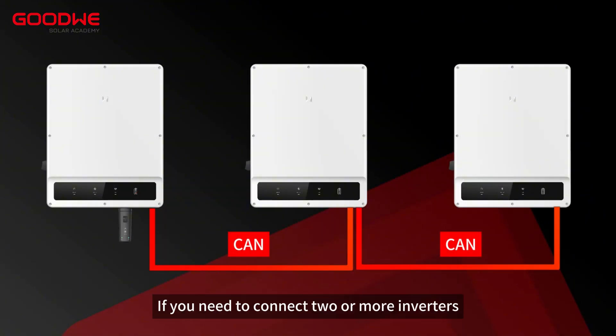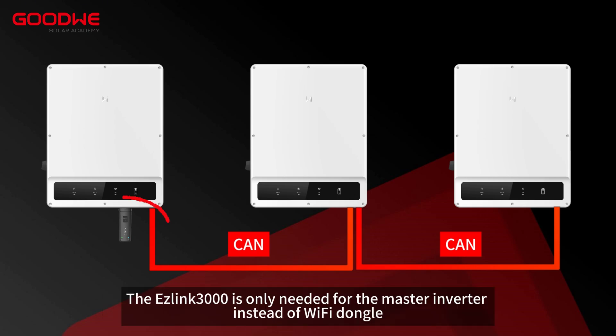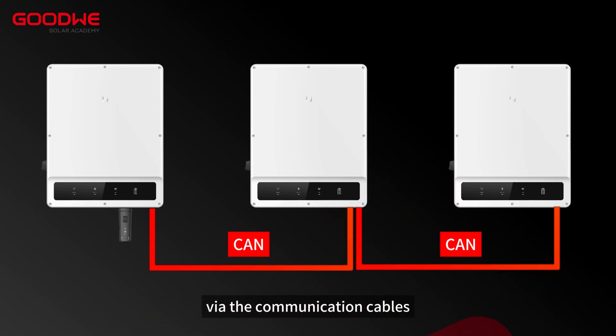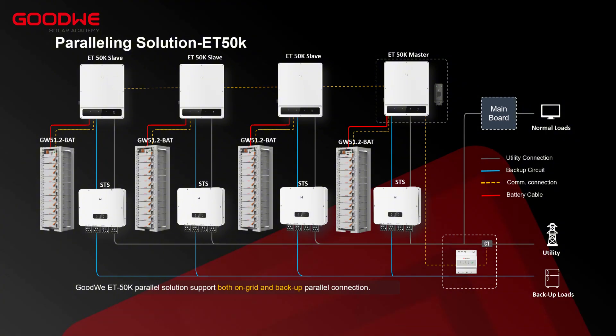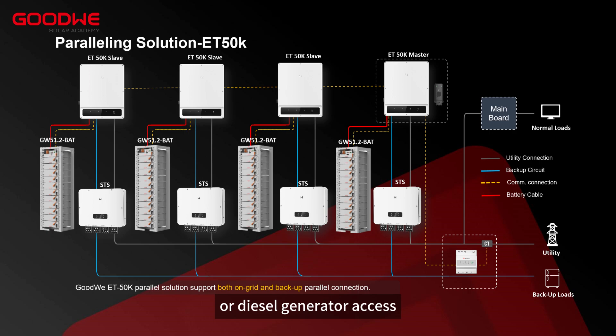If you need to connect two or more inverters, the master and other slaves need to be installed separately. The EZlink3000 is only needed for the master inverter instead of a Wi-Fi dongle. The master inverter issues commands to the slave inverters via the communication cables. This solution supports up to four inverters in parallel. If the on-grid and off-grid switching function is required, or diesel generator access, STS needs to be installed.